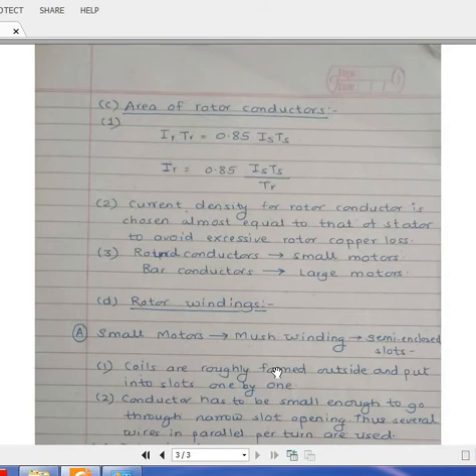How you can write down MMF? Stator rotor MMF is ampere turn. So it is IR into TR which is 0.85 times IS into TS. So your IR is going to be 0.85 IS TS divided by TR. Why we have calculated this IR? Because always while deciding area, we have to consider current density. Current density for rotor conductor is chosen almost equal to the stator to avoid excessive rotor copper loss.